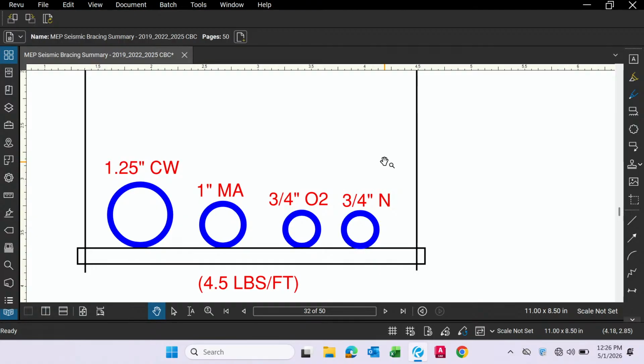But again, if you took note, there was an exemption based on size when it comes to piping with an importance factor of 1.5. Anyone remember what size is exempted for 1.5? 1 inch or less, right? So this one, 3/4, doesn't need to be braced, even though it's 1.5. This one, 1 inch, we already said it's medical air, it's clean air, so its importance factor is 1.0. And this one, 1.25, cold water, nothing hazardous. So based on that, none of these pipes need to be braced, right?